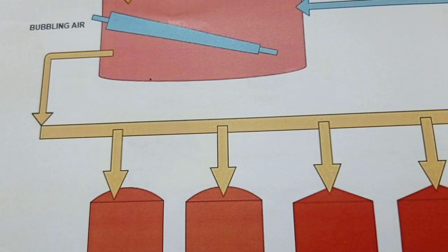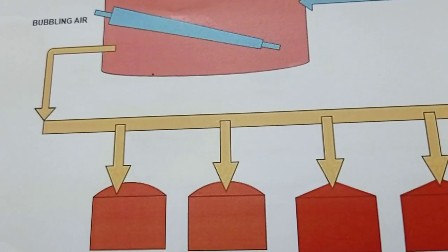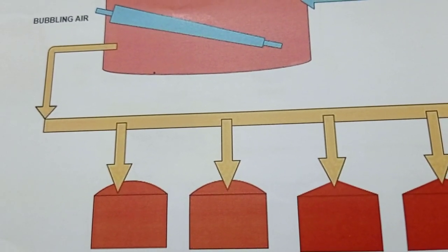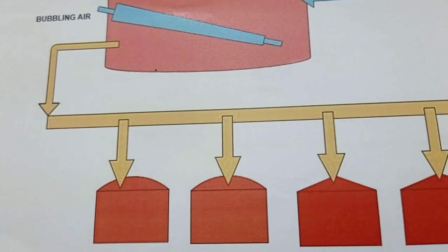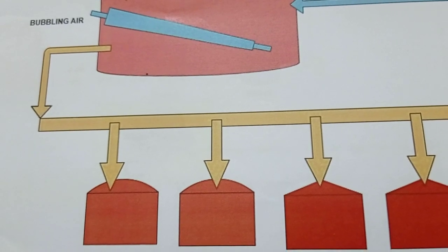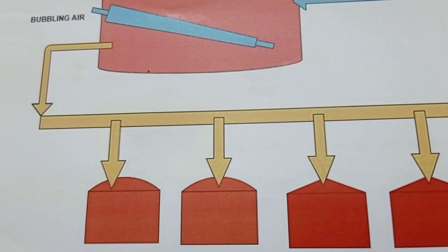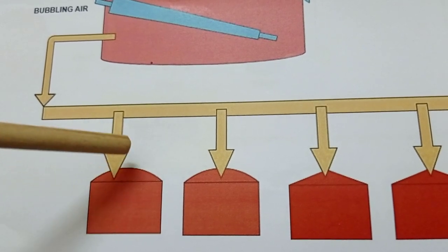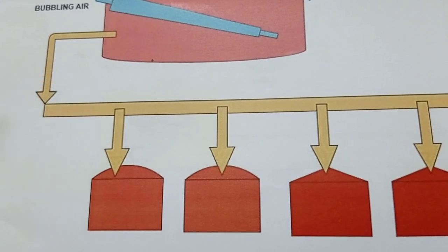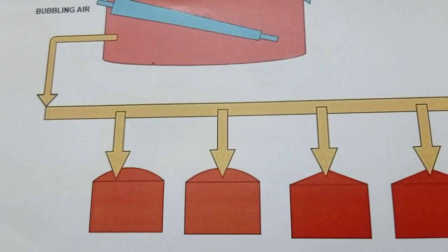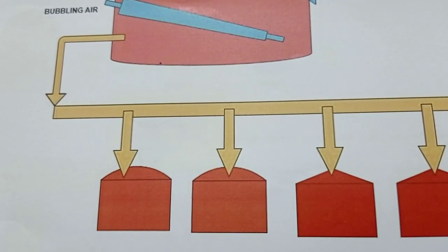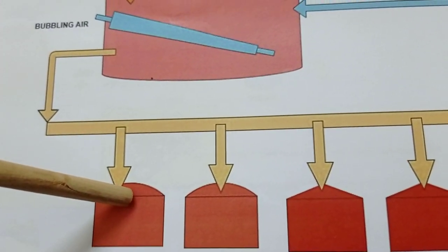Generally submerged pumps are used, and some companies use vertical or horizontal, depending upon the design, the space and your plant design. For level transmitters we use different types, not differential, but bubbler type. Any storage tank will have one blind vent which we open to take a manual dip, to check whether the level transmitter is good or not. So it is better to have a manual dip. So this is about this.